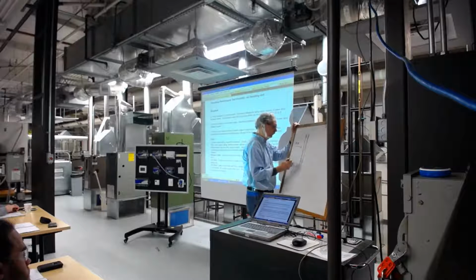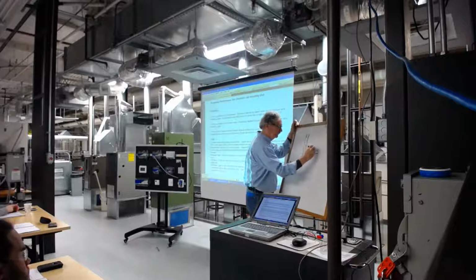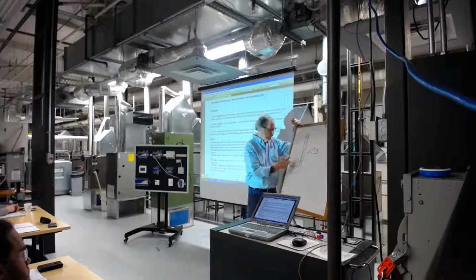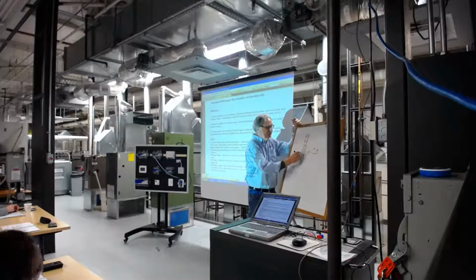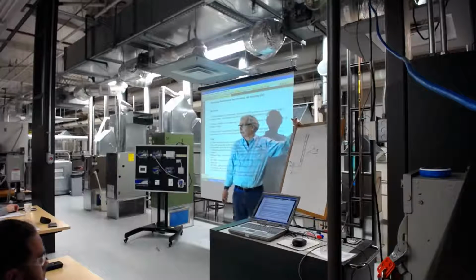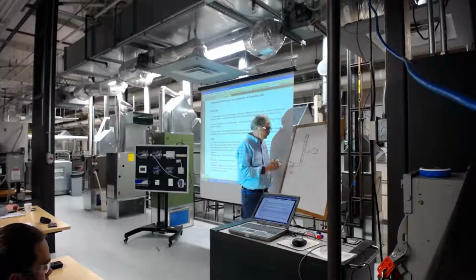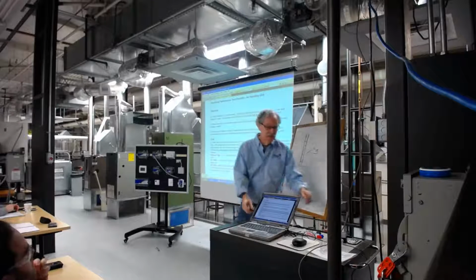Oops, I got it the wrong way. So you've got a coil, you've got 45-degree water coming in. Of course, you're going to have some passes, and if you're at full load, you might get 55-degree water out. 10-degree delta, right?